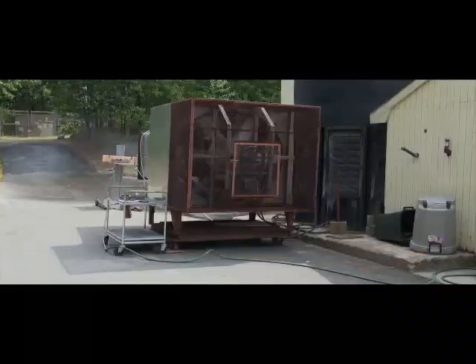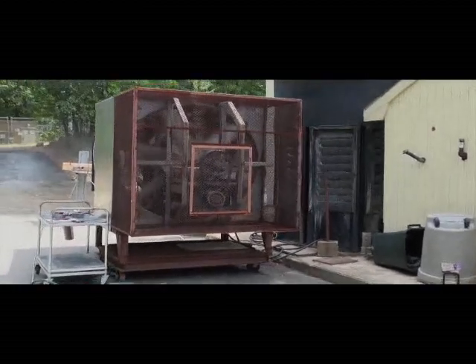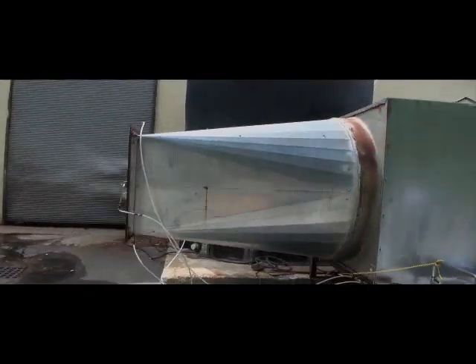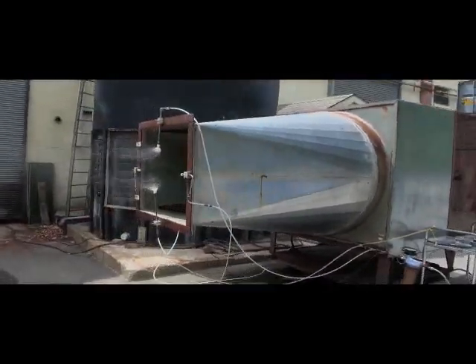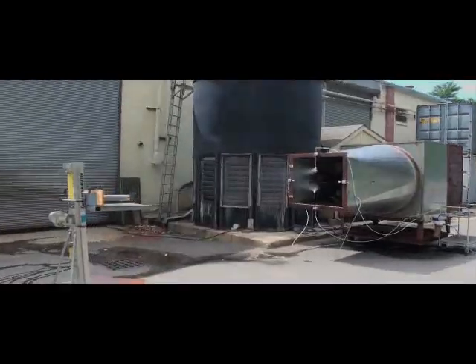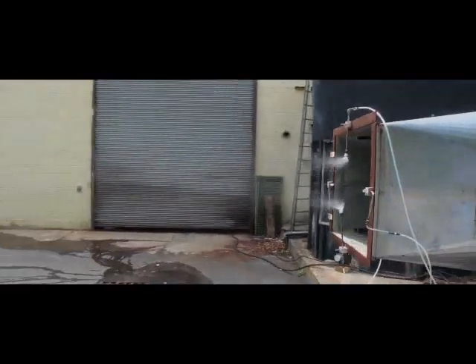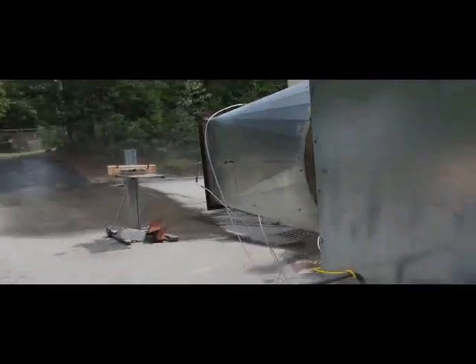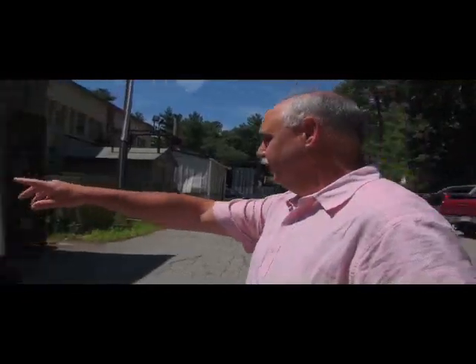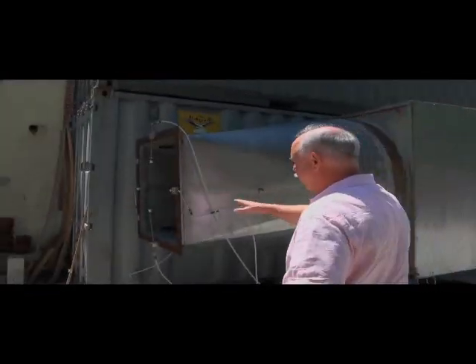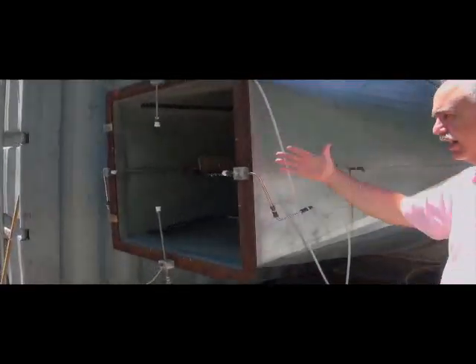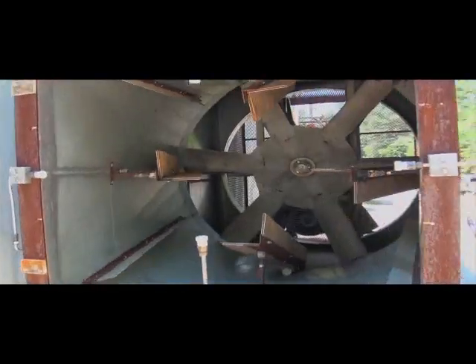This is our wind-driven rain test. So we're going to mimic wind speeds, wind-driven rain of around 75 miles an hour. So it will be used for a variety of telecommunications, outdoor work. We've done some work with the New York Transit Authority and some of their switching equipment. So we have water sprayed at a known rate that's put in over here, and the test article will be out at a given distance.